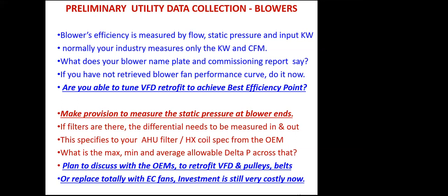It is not visible. A compressed air pressure drop is visible to everyone, and they have a compressed air pressure gauge and a pressure switch at the tail end. It will give an alarm. But for the blower, we have not seen this, because we have not used the digital static Pascal meter. It is just costing 8,000 or 10,000 rupees for the portable meters. It can even be fixed on some of the bigger blowers, 50 HP and above, which can have an in situ digital Pascal meter, so that we know what Pascal we are operating at.